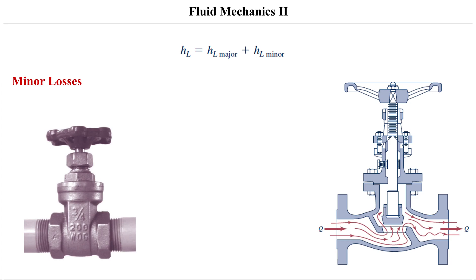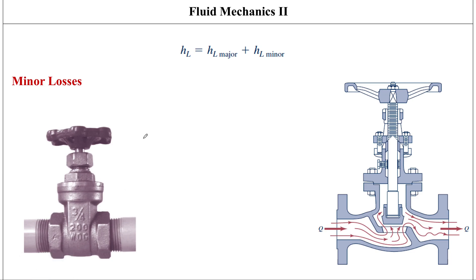These types of losses are very difficult to account for — there's no theoretical way to do it yet. All the head loss information for these components is based on experimental data in dimensionless form. One of the methods we use to determine minor losses — head losses or pressure drops — is to specify something called a loss coefficient, represented by KL.